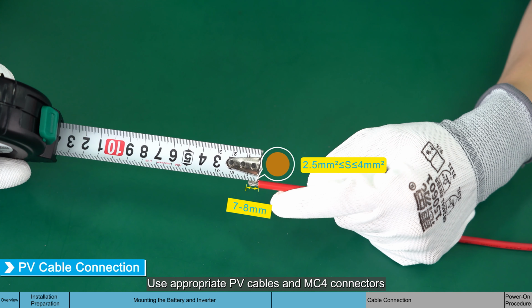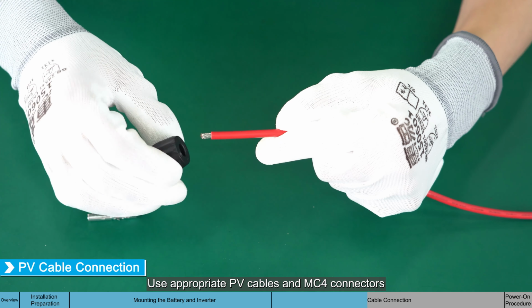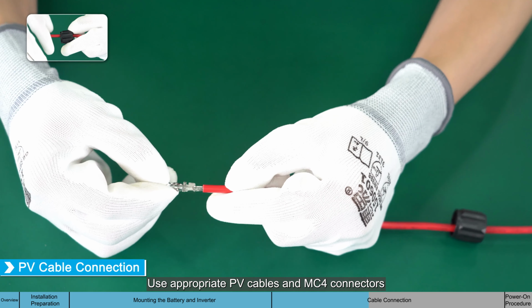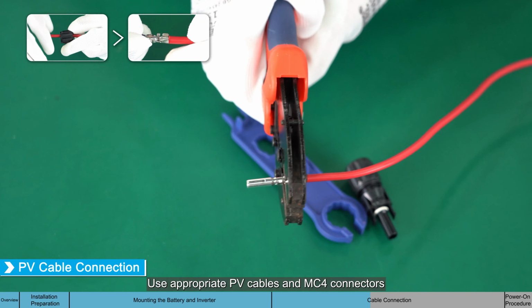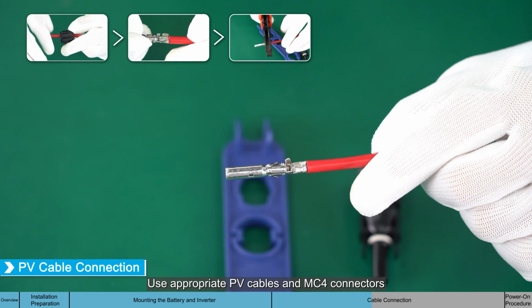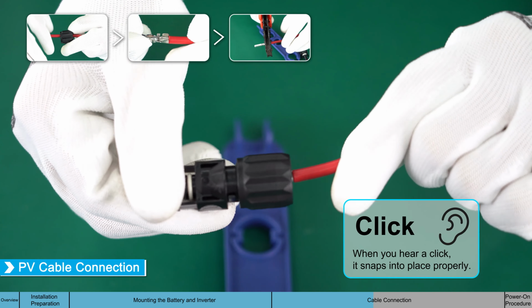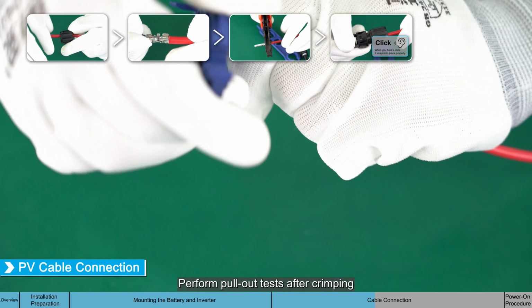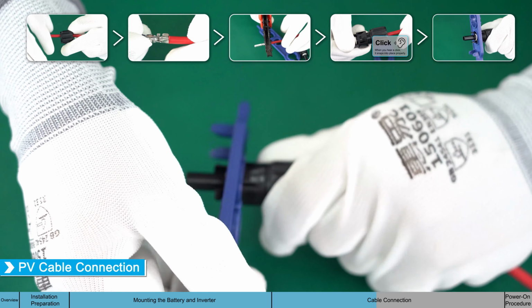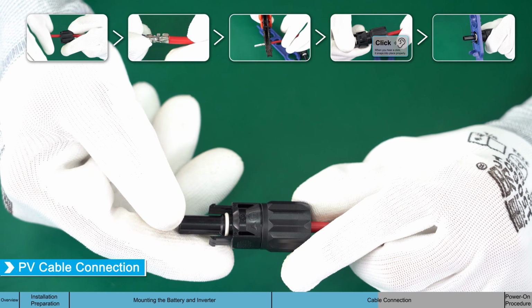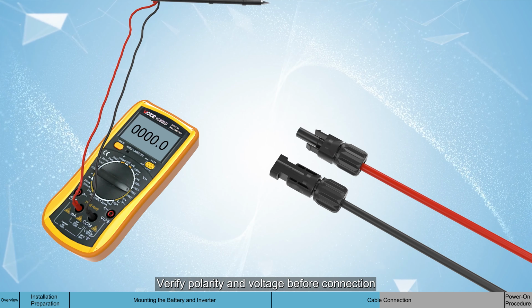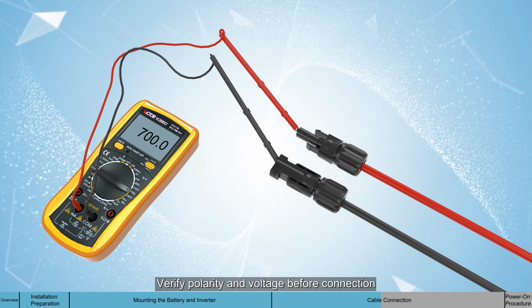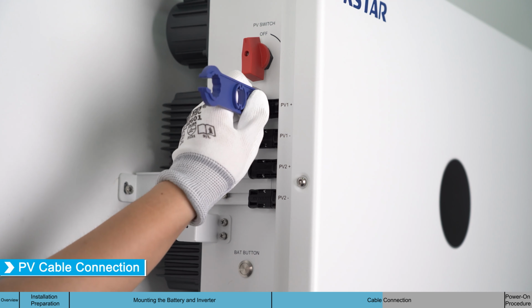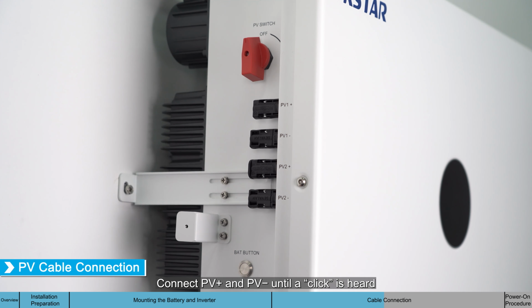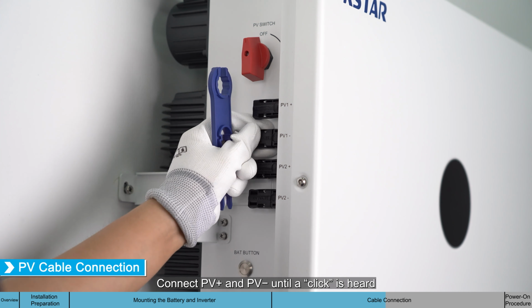Use appropriate PV cables and MC4 connectors. Perform pull-out tests after crimping. Verify polarity and voltage before connection. Connect PV positive and PV negative until a click is heard.